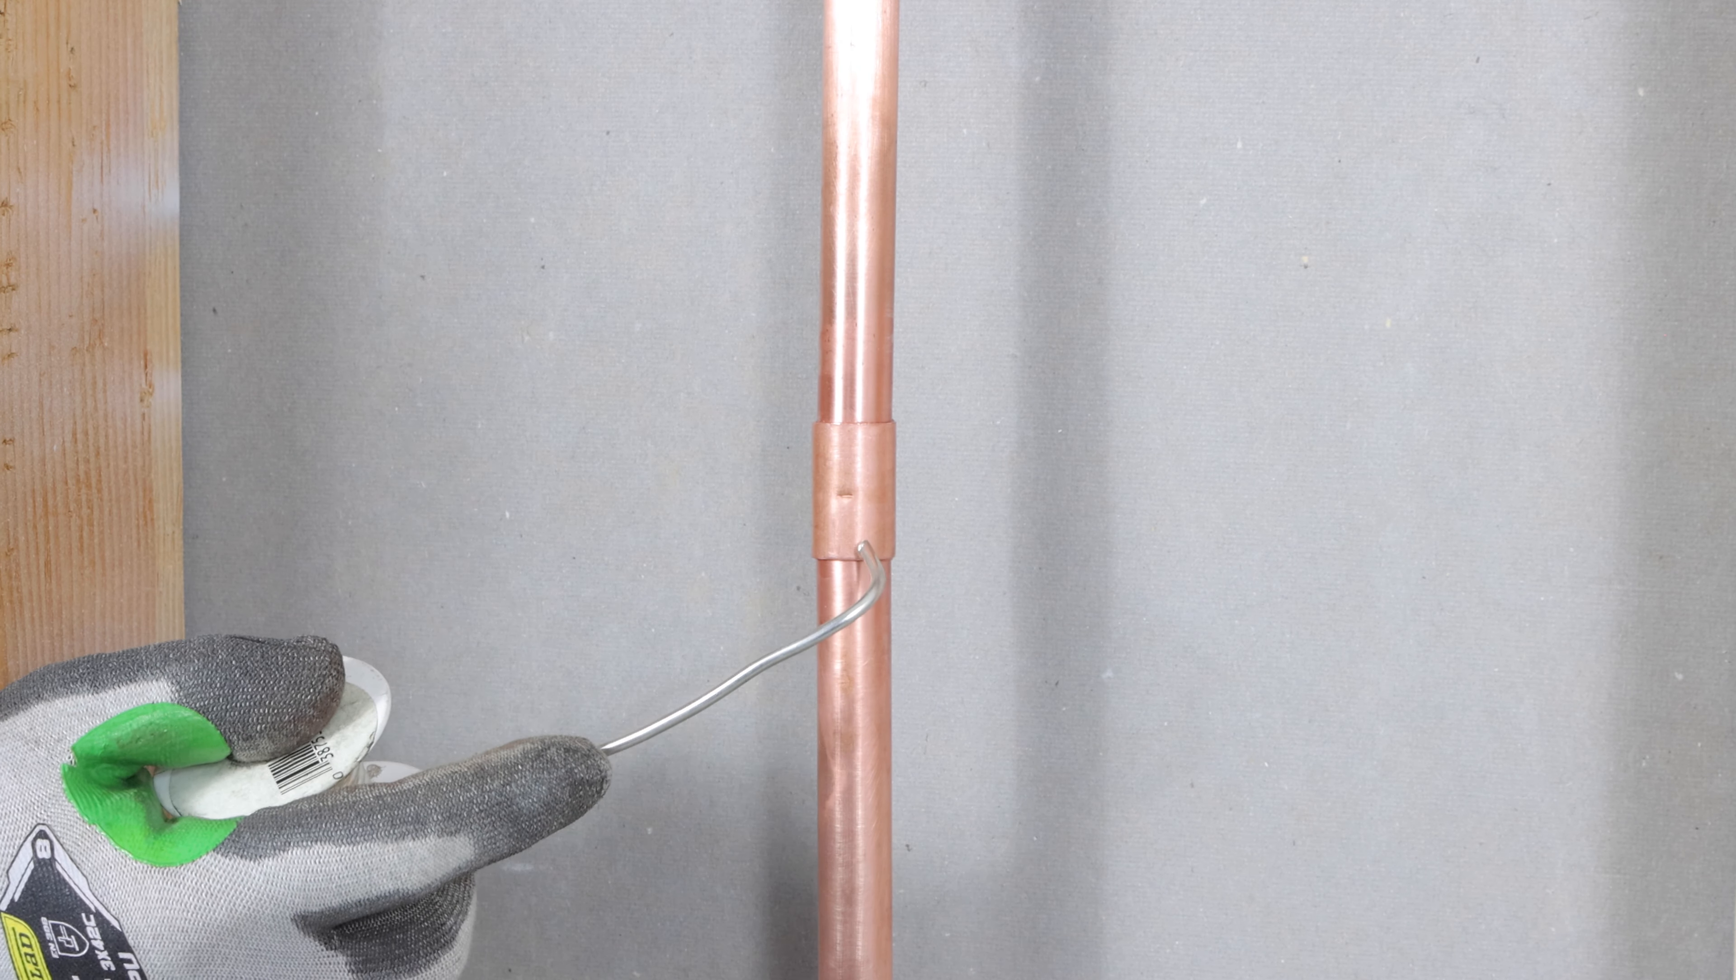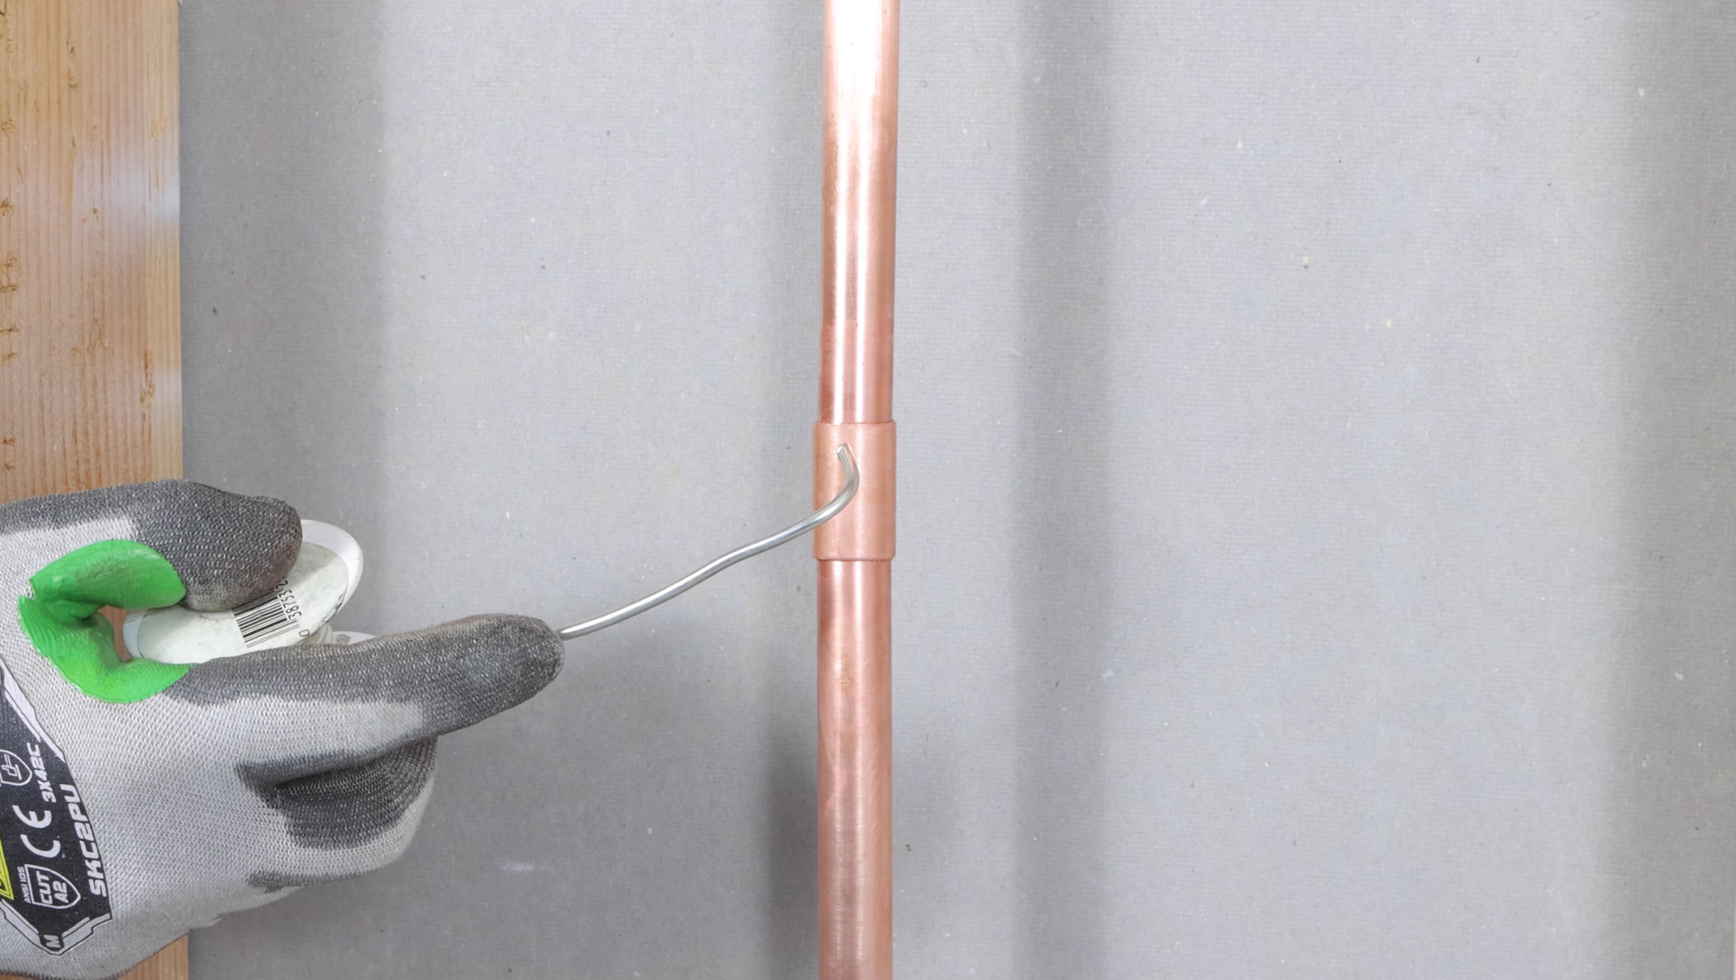The general game plan is to start by preheating the pipe, heating the coupling, and then by the time you get to the top, you're not really going to have to apply a lot of heat at all. I also like using a flame protector pad. I put that inside the wall.